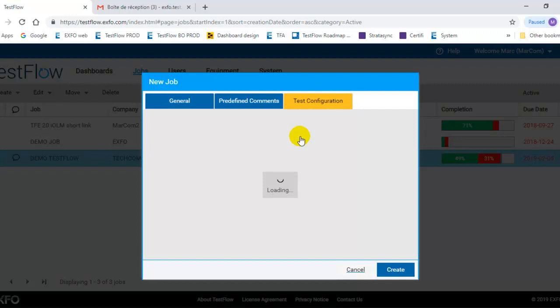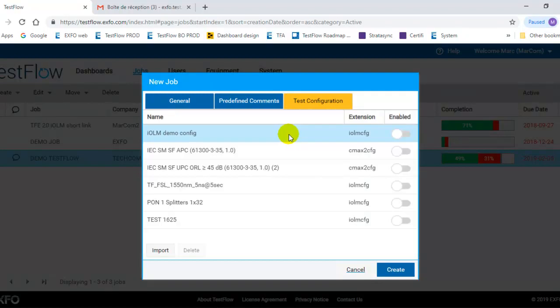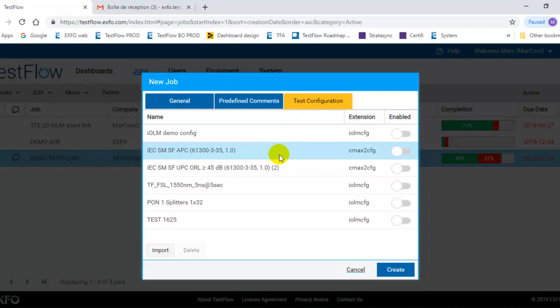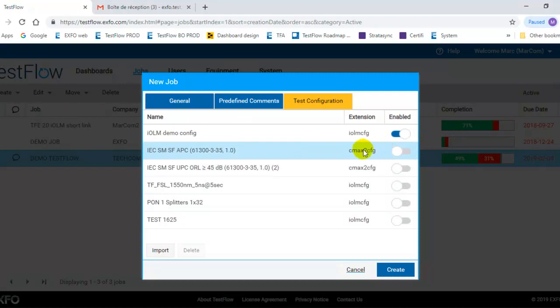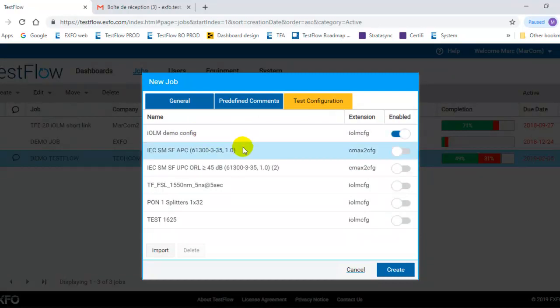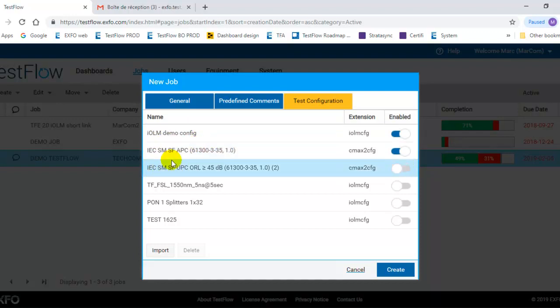Test configuration. So you can force test configuration to be pushed to the tester. So when the person in the field receives a job, he doesn't have to set the threshold, the testing parameter. This can be done directly from the server. So basically here I can, okay, I know it's going to be an iOLM job. Then I'm going to enable that specific configuration that I want the user to use to execute that job. Same for the FIP here. So I can select the IEC standard that reflects the connector type that would be needed for that specific job.